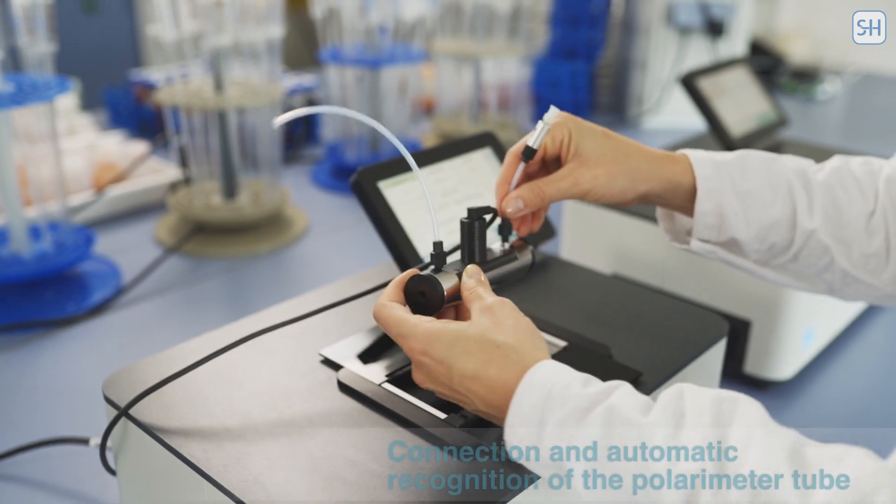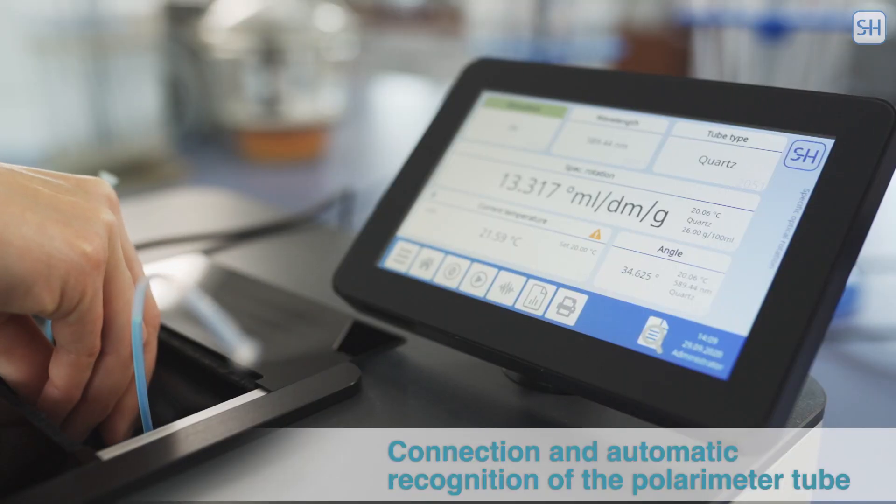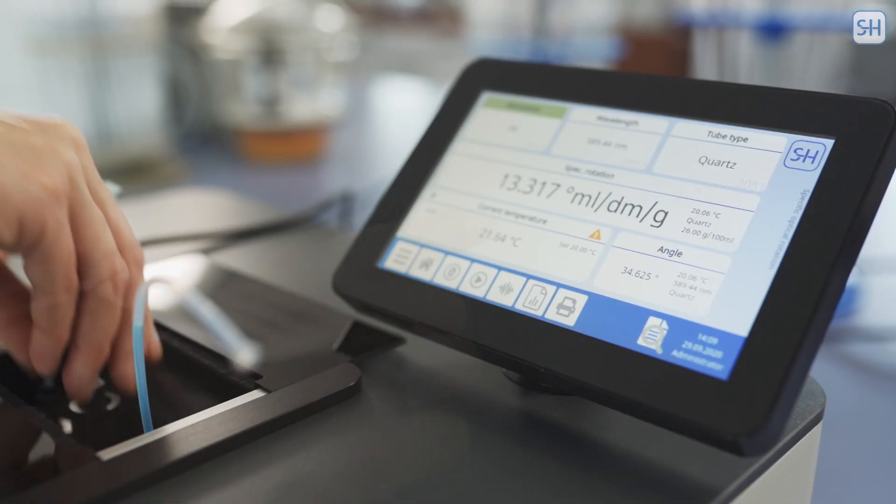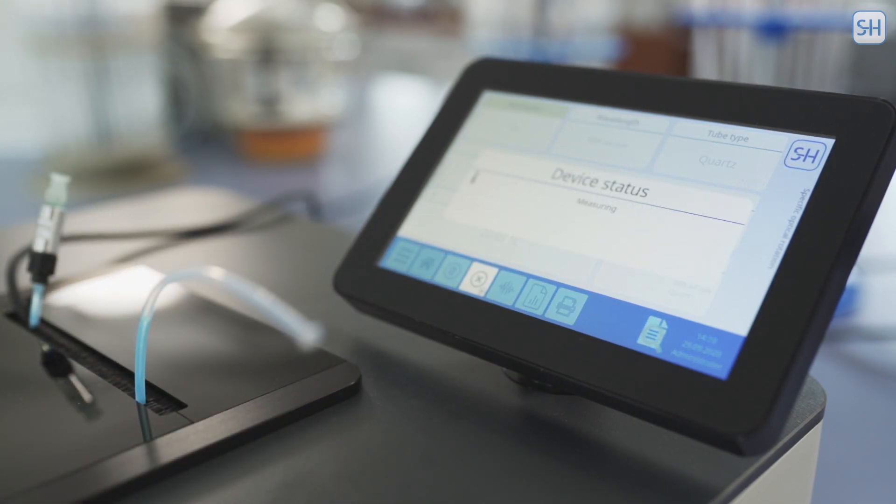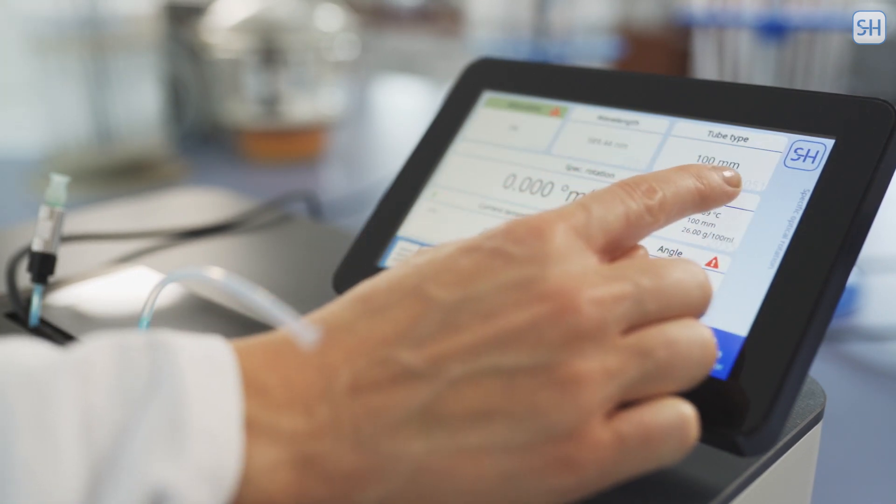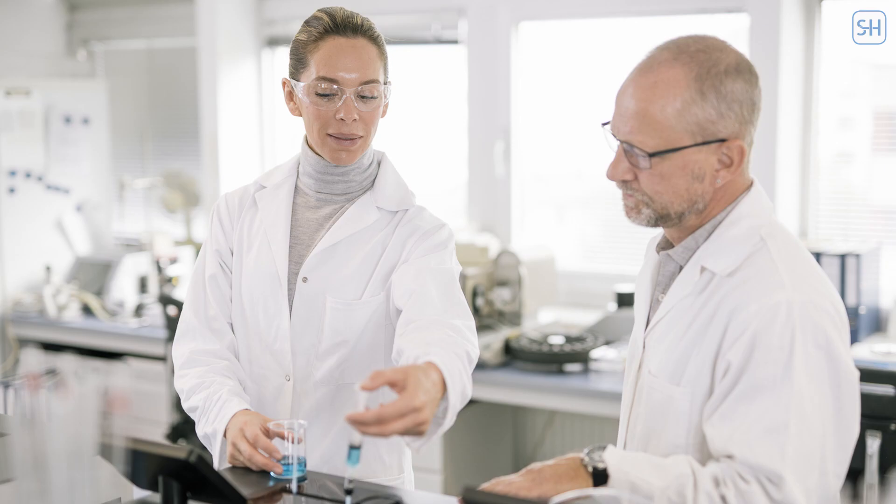Sample handling is made easy throughout the entire instrument and our automated recognition of Polarimeter tubes and quartz plates make the calibration of the instrument very simple and allow you to immediately trace your measuring results.